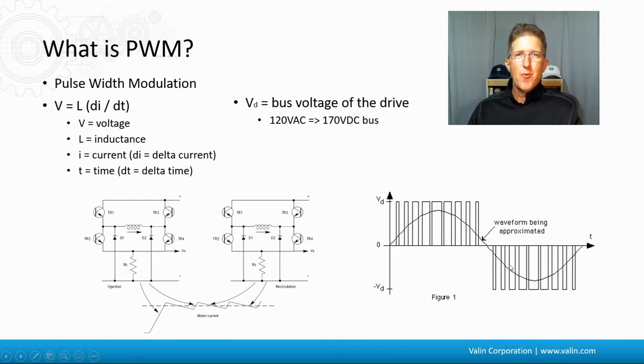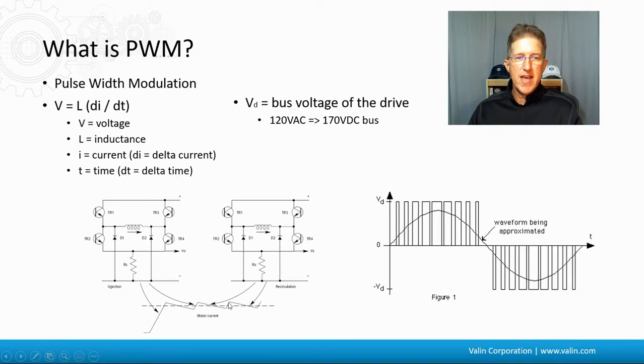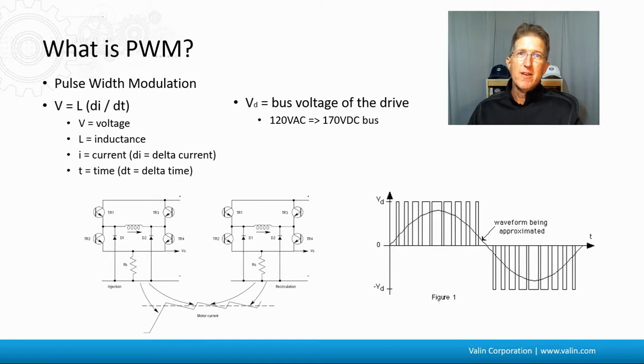As the motor moves, the current approximates an AC sine wave. There's some terminology that tends to confuse people — is it an AC motor? A servo motor is a type of electric motor, and a servo drive is a type of drive, but a servo motor approximates an AC sine wave as the motor is moving. You can see here, as the transistors in the H-bridge are changing, the current goes up and down as it's controlled. How quickly that's controlled has to do with the inductance of the motor and the chopping frequency of the drive. If you have a low inductance motor, that current can change very quickly and you need a high frequency drive — that's why I worked with a 40 kilohertz drive, because that motor had a really low inductance, and matching them was very important.